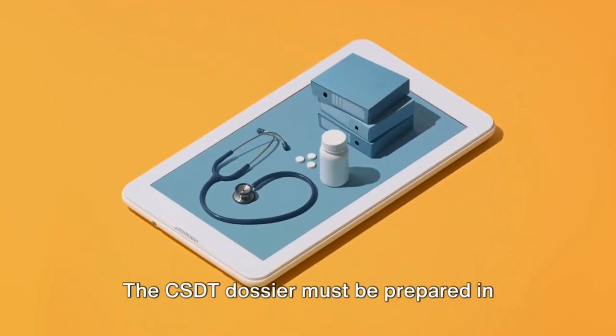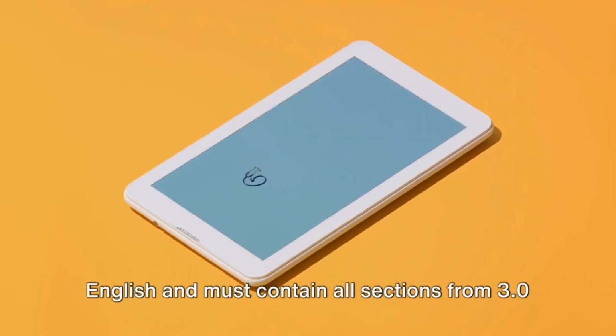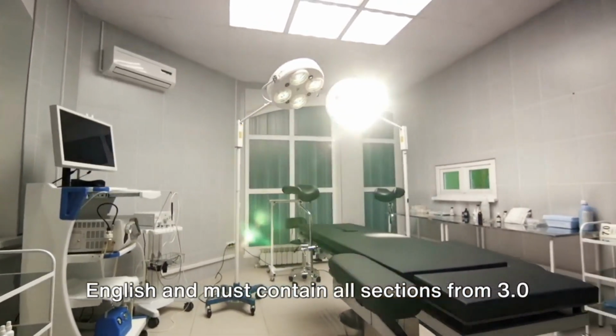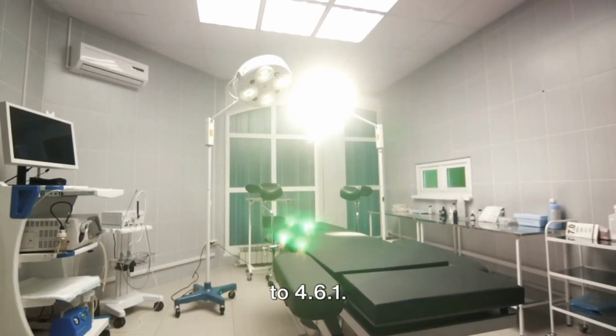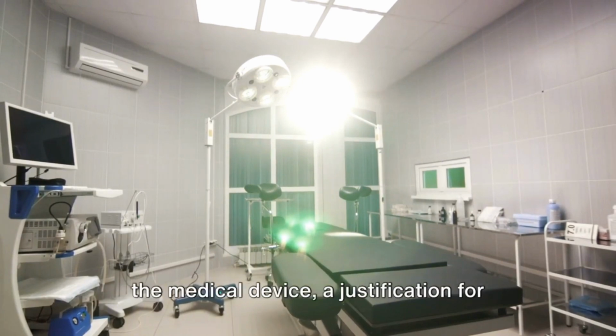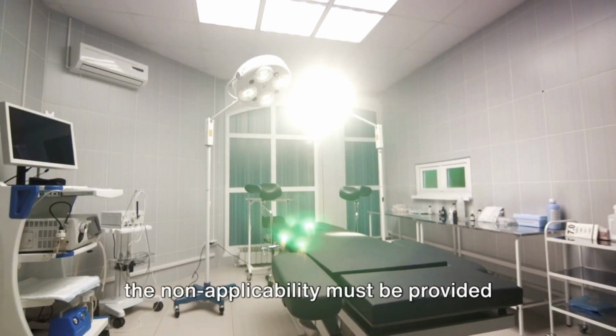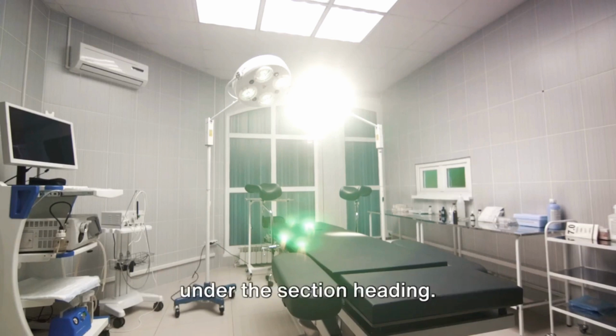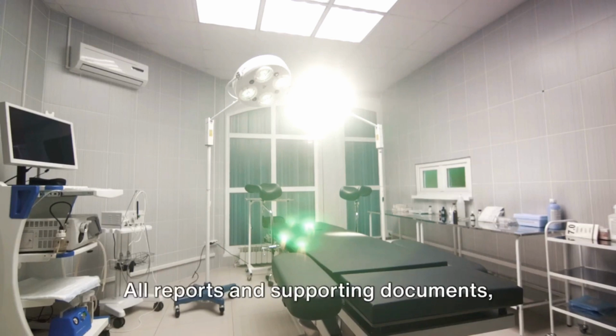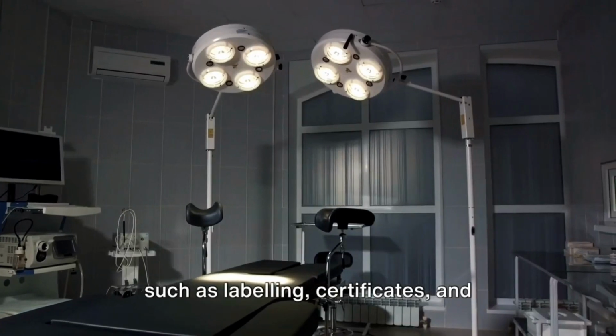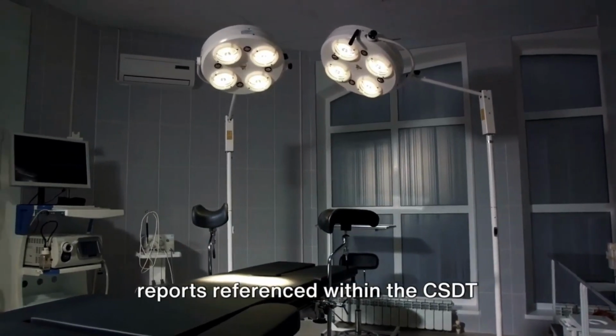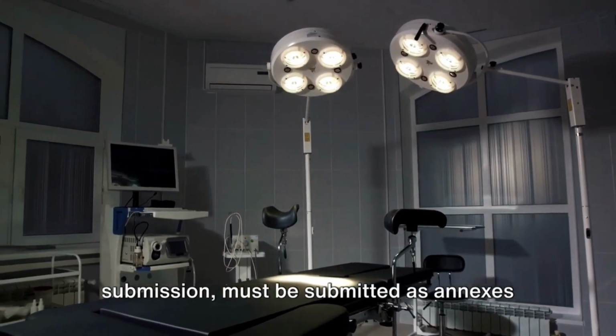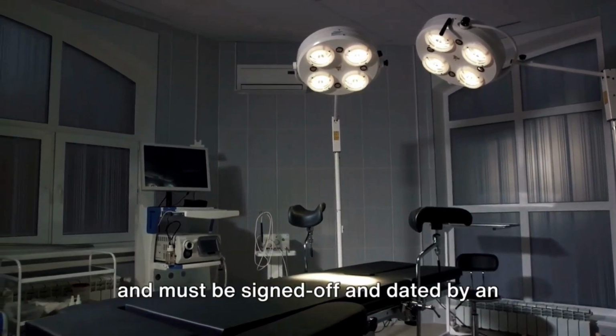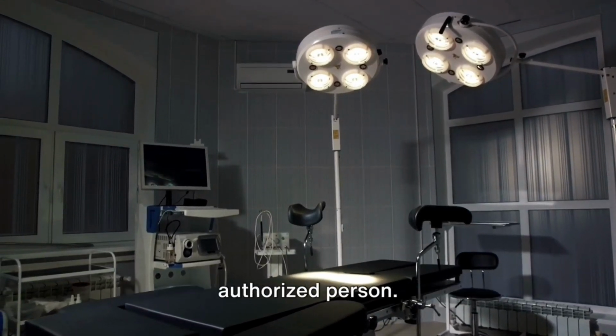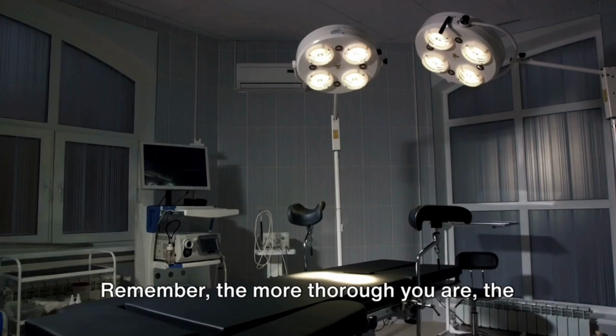The CSDT dossier must be prepared in English and must contain all sections from 3.0 to 4.6.1. If certain sections are not applicable to the medical device, a justification for the non-applicability must be provided under the section heading. All reports and supporting documents, such as labeling, certificates, and reports referenced within the CSDT submission, must be submitted and annexed and must be signed off and dated by an authorized person. Remember, the more thorough you are, the smoother the process will be.